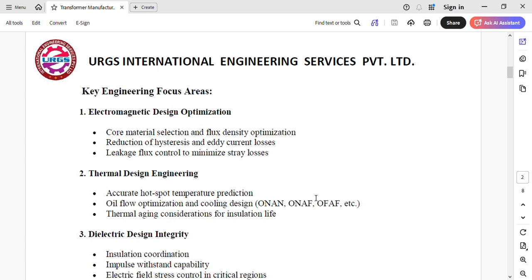Now, key engineering focus areas. First, electromagnetic design optimization. Here, core material selection and flux density optimization, reduction of hysteresis and eddy current losses, leakage flux control to minimize stray losses. Second, thermal design engineering: accurate hotspot temperature prediction, oil flow optimization and cooling design, ONAN, ONAF, OFAF, etc. Thermal aging considerations for insulation life.